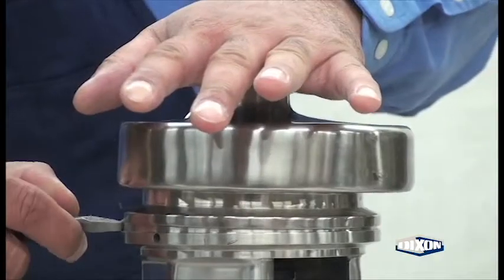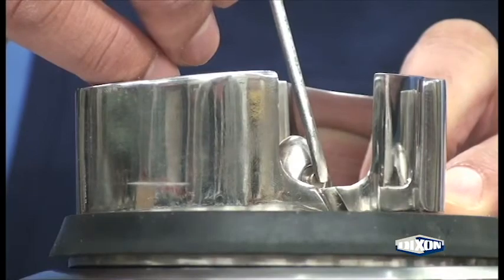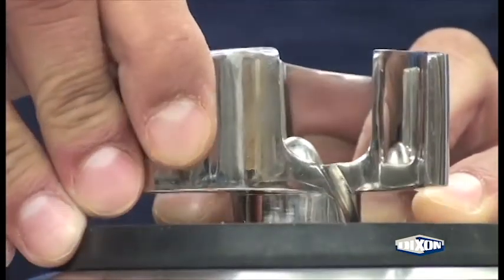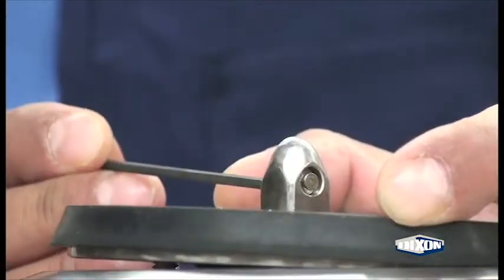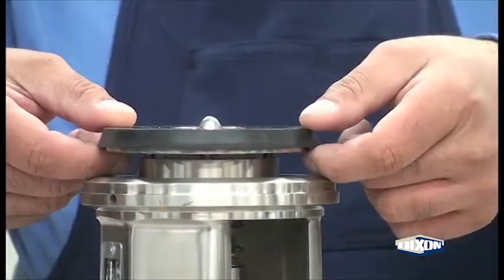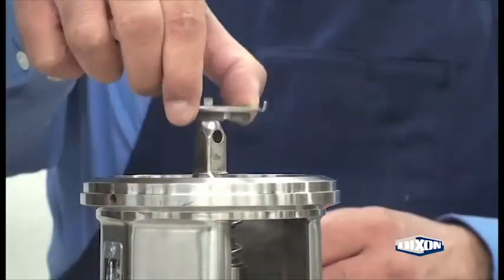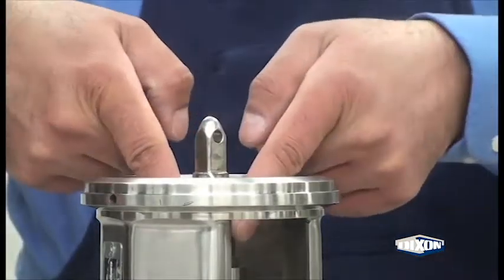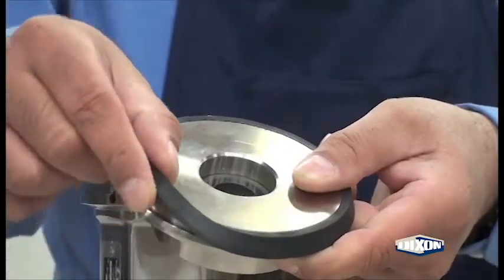Remove the guard assembly, loosen the wing nut and remove the clamp assembly. Remove the volute, center the impeller retainer on the stub shaft, remove the impeller, remove the retainer, and lift off the backplate.